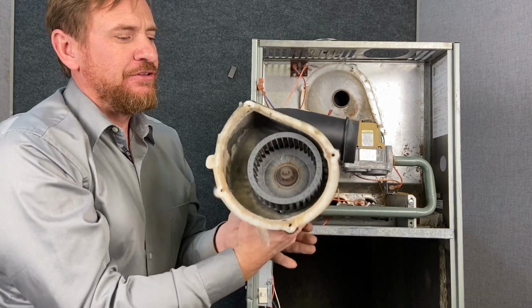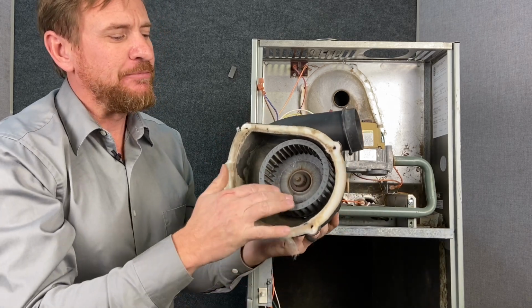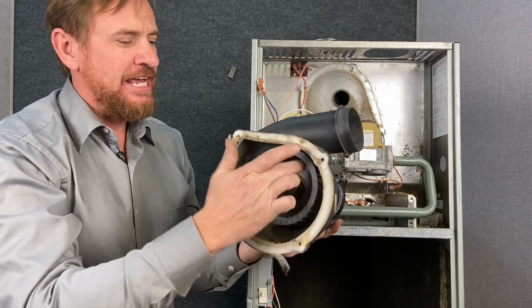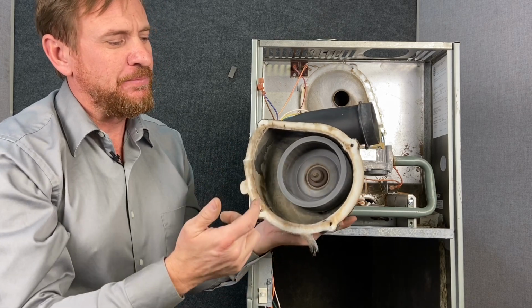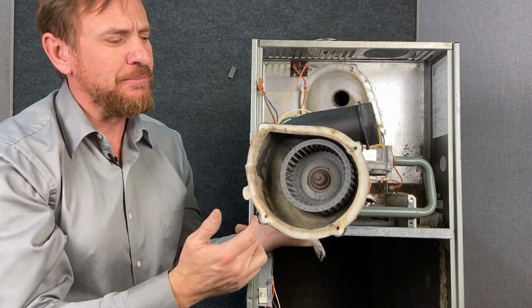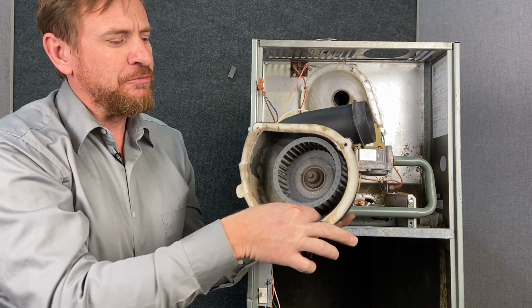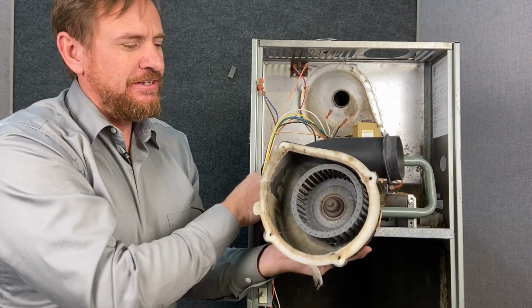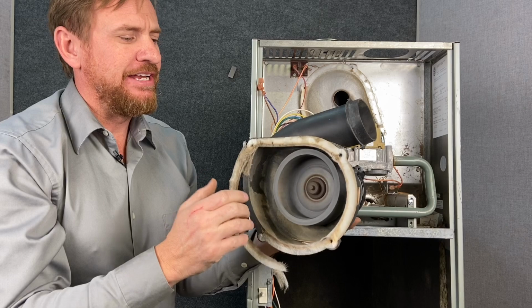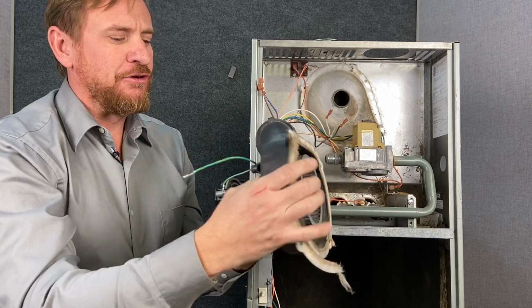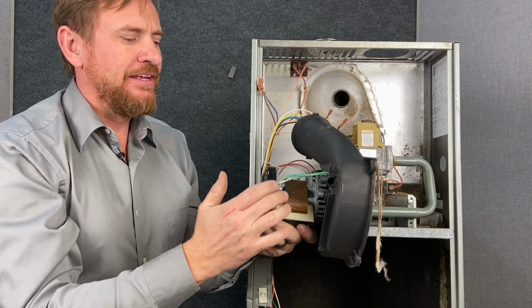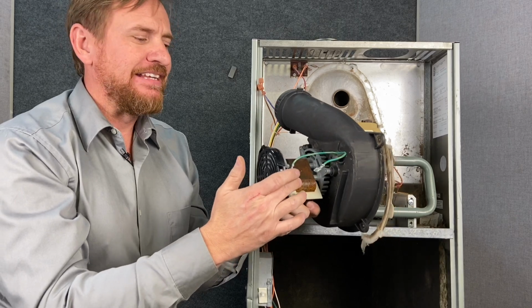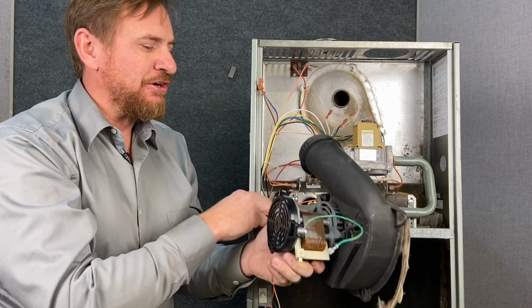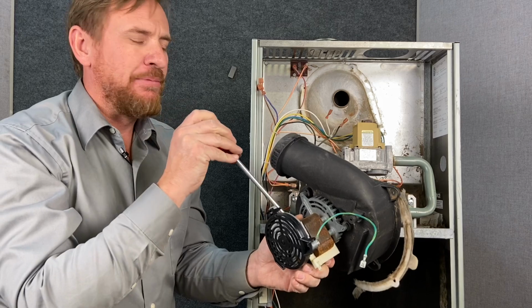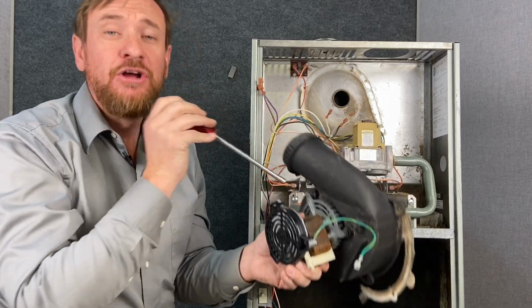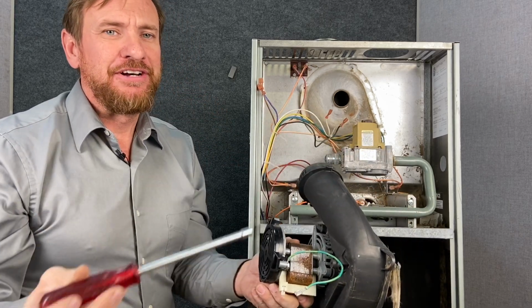So this is our inducer fan, or inducer draft motor. It's pulling a draft through the heat exchanger. If I turn this, it turns pretty free, but notice how it comes to an abrupt stop. That tells us there's probably some damage to the bearings. The bearings are probably overheated. One of the things I like to do when this motor runs is I'll take and put a mechanic stethoscope against this and listen to the sound of the bearings. In the old days, we used to actually take a screwdriver, put a screwdriver against it and put it up to your ear, which does work, but looks really funny in front of your customers.